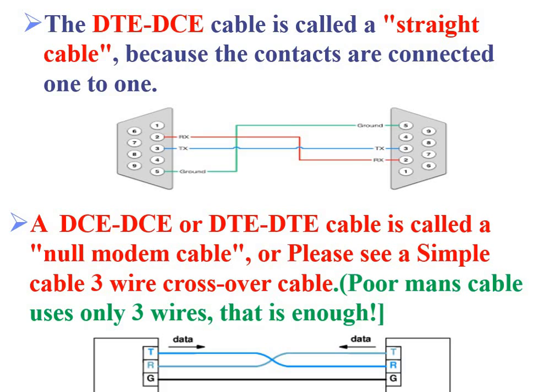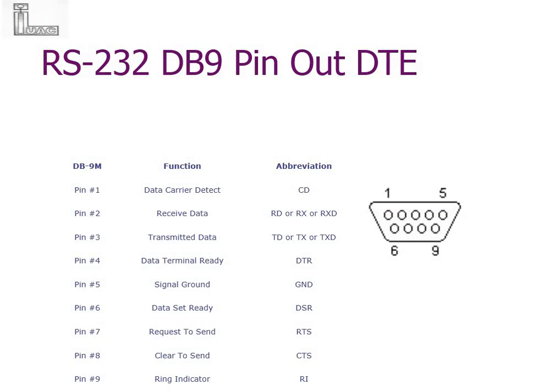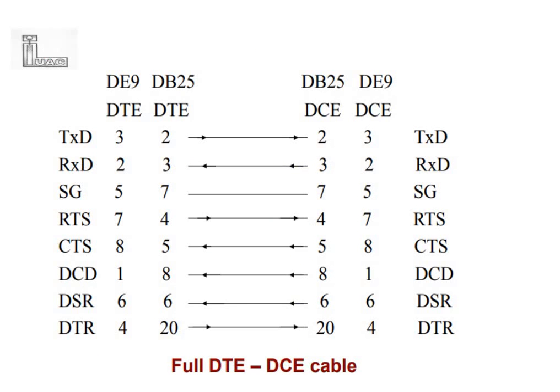Whereas when DCE-DCE or DTE-DTE communication takes place — for example, my computer is a DTE and my temperature meter is also a DTE — I need to make a null modem cable: transmit goes to receive and receive goes to transmit. This is how the DTE pin diagram looks. There are nine pins in the connector; you need three wires for basic communication: pin numbers 2, 3, and 5. Sometimes people also use a 25-pin D-connector for RS-232.